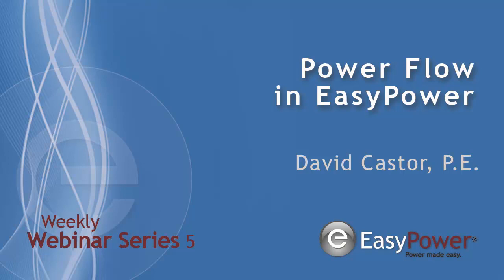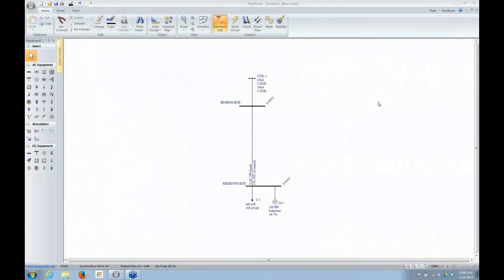One of the things that's important to understand is that the power flow calculations that EasyPower does, or any other software, are different from the load calculation that you would be required to do for equipment design per the NEC or some other standard. So those are really two different things.